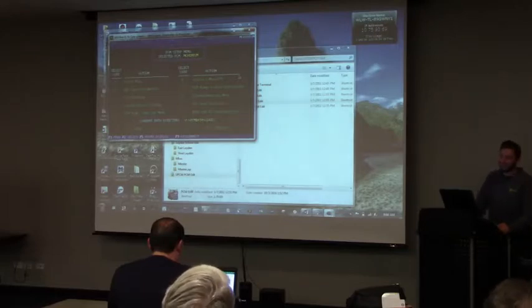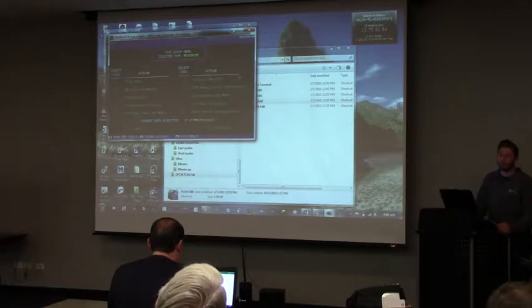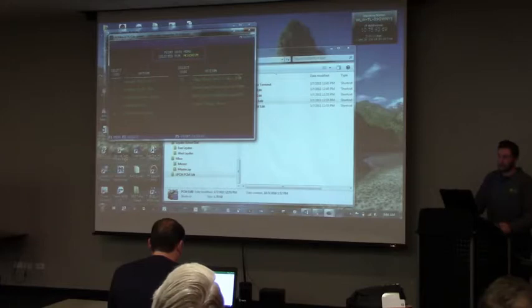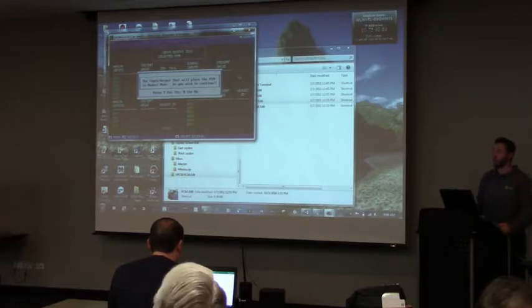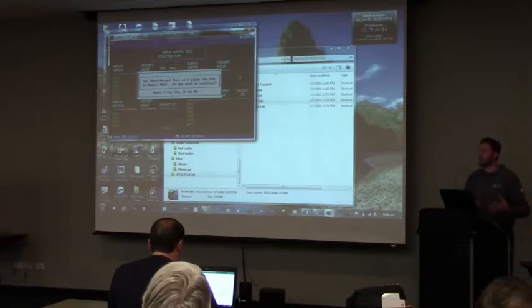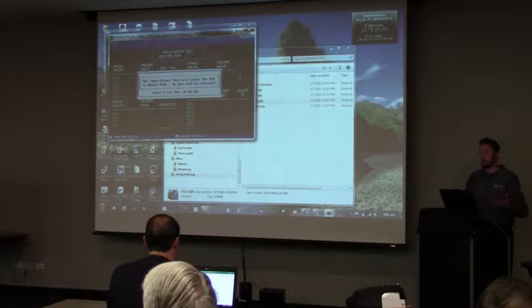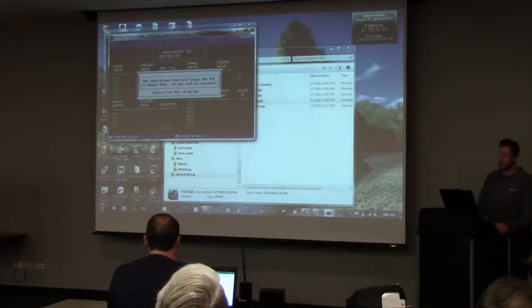One thing that's nice on this, at least coming from the service end, is they have a test mode for PCM and UPCM. So if you go back to point data, you actually do IF2, which is input-output test. And it's going to say you're putting this in a manual mode, and once you're done, you want to make sure you release that back to the mode it was in. So you just gotta be careful with that. So I'm going to hit yes, I really do want to put it in manual mode.